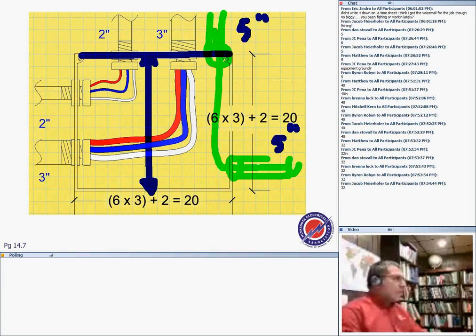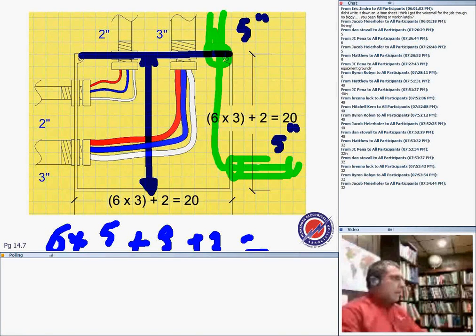It is top to bottom. It says 6 times the largest conduit engaged in a U-pull. Which one is the largest? It could be engaged in a U-pull, by the way: 2, 3, and 5. That's a lot of conduits in the same wall. 30 plus 3 plus 2 is 35. That will give me 35 inches tall.